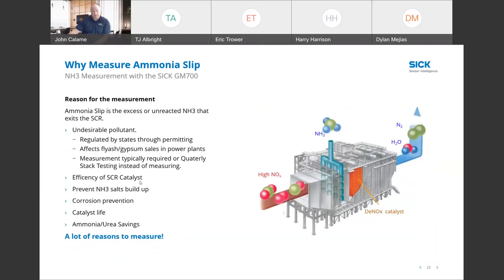So we pretty much talked about the benefits of having proper injection control. One was, if you have too much of the chemicals in there, you can cause corrosion. And we talked about the catalyst life, and some of these catalysts are very expensive, several $100,000. So you can extend the life of that. There's a definite ROI calculation on that to provide significant cost savings. And then, of course, the storage of ammonia and the actual product itself is not inexpensive as well. So if you can reduce the amount that you use, you're going to reduce the total operating costs of the removal technology.